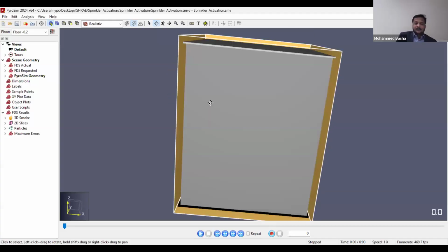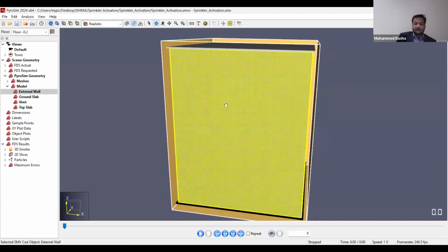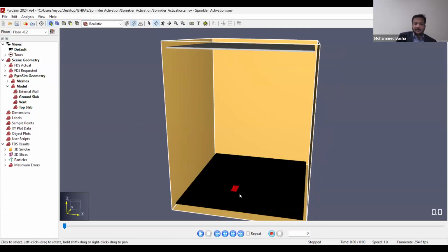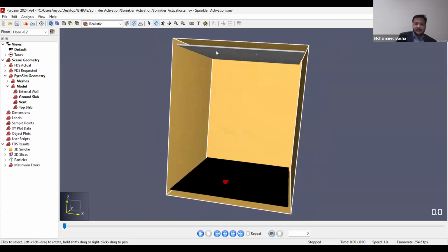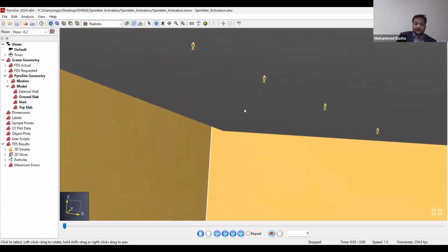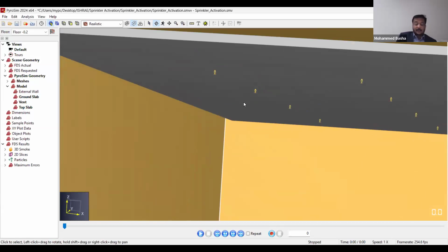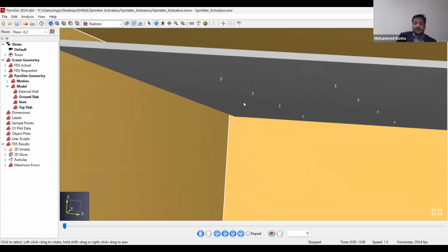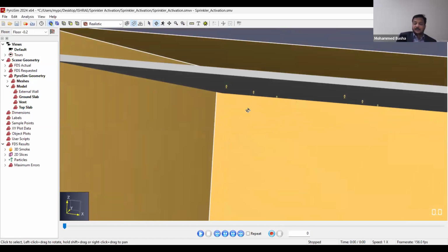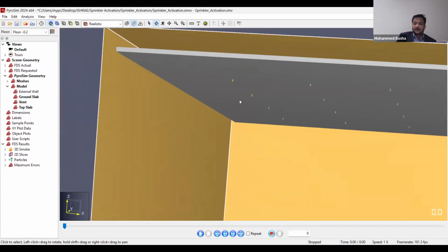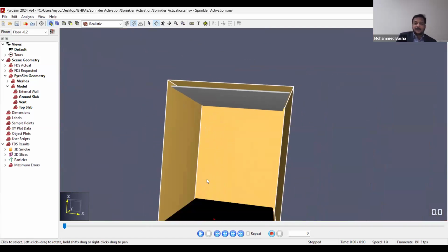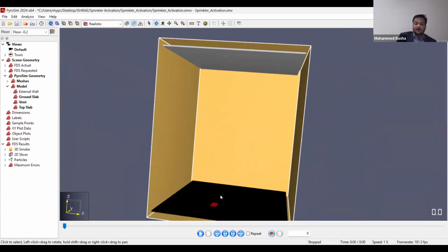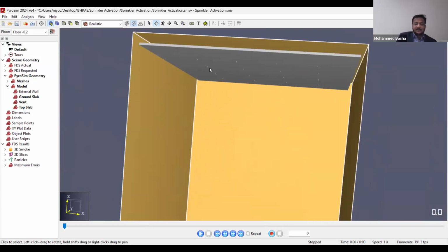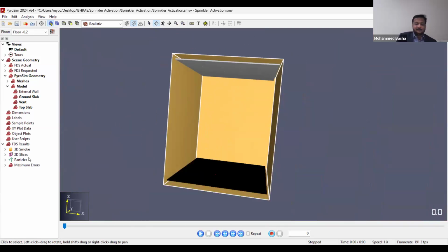Okay, I assume a big hall, 20 meters high, and I put a fire here, and you can see the sprinklers. Pendant sprinklers are perfectly fine. Do not think that you need to have an upright sprinkler only. Pendant sprinklers and upright sprinklers both do the same job. It depends upon what location you want to use. Now I have assumed a medium growth fire. Then I want to see whether the sprinklers are activating or not. So let me show you.